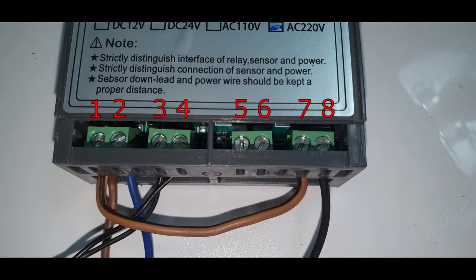When cooling, power is fed to the compressor through ports 7 and 8. The phase is provided to port 7, and port 8 is connected to ground in the electrical box at the bottom of the freezer.